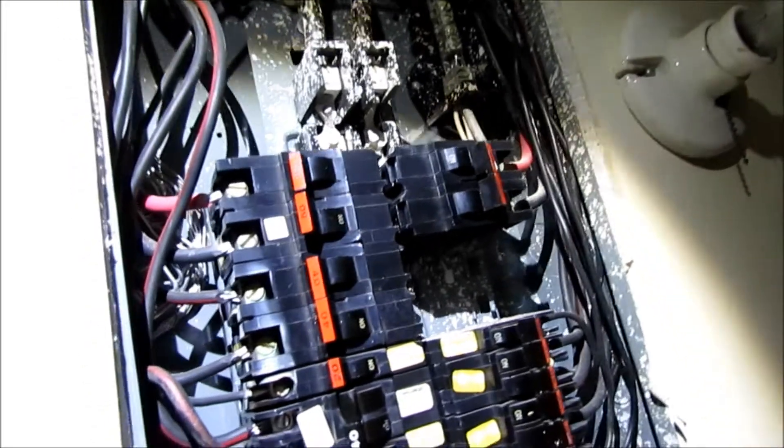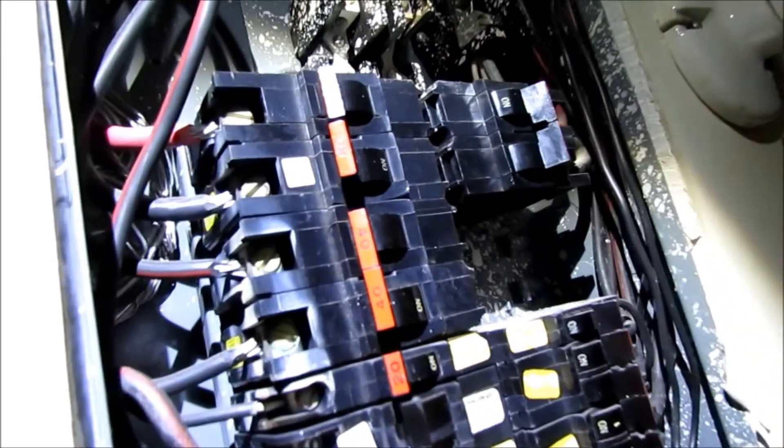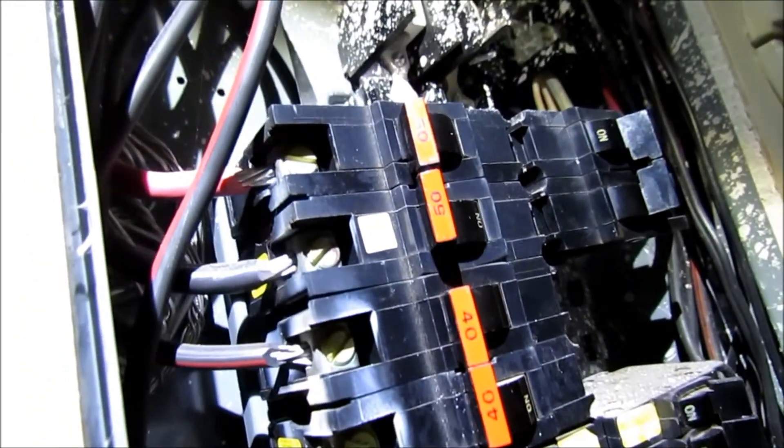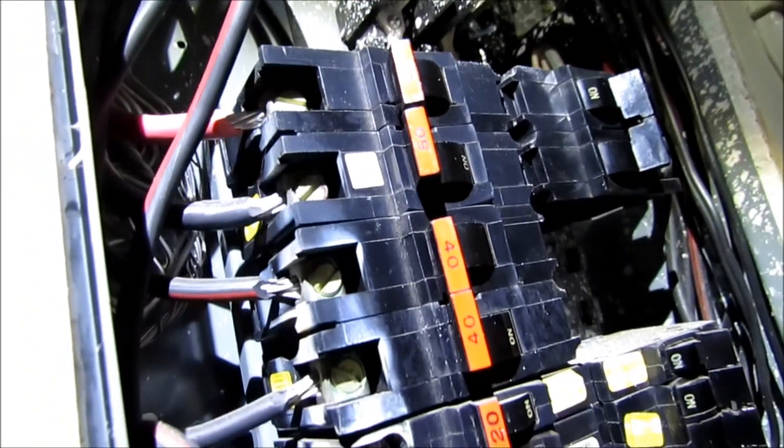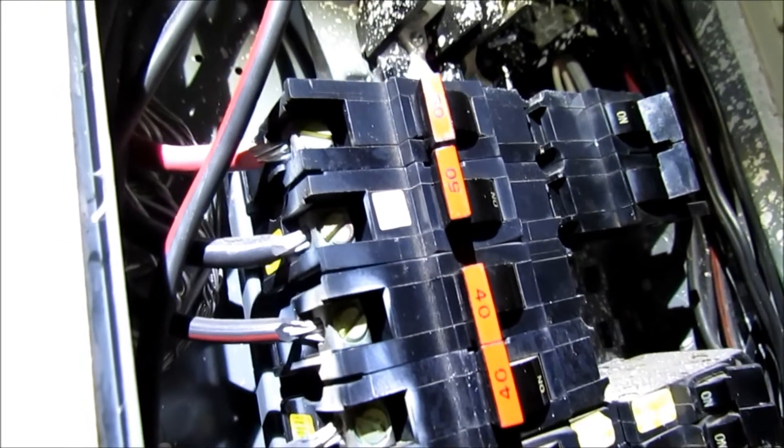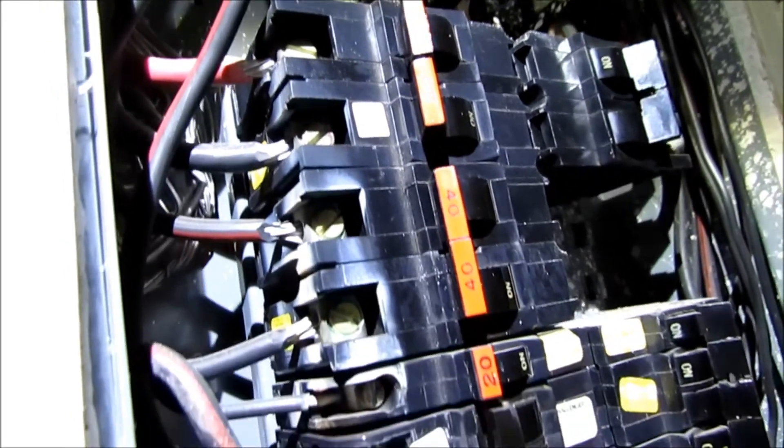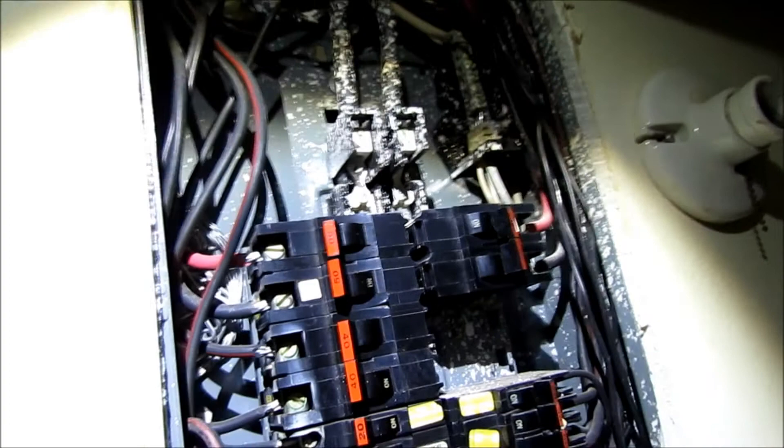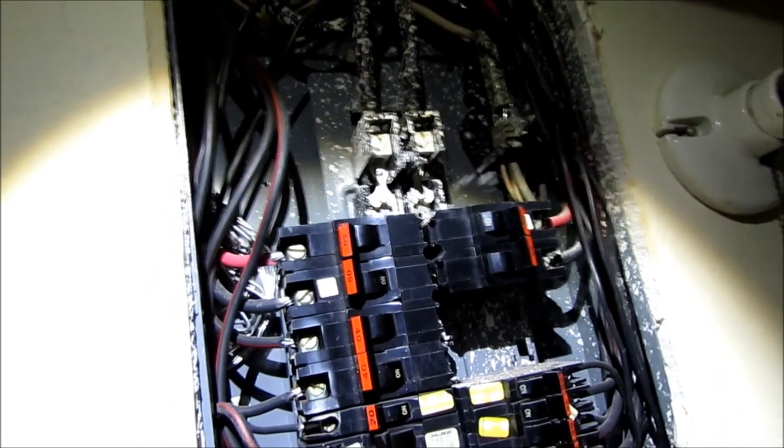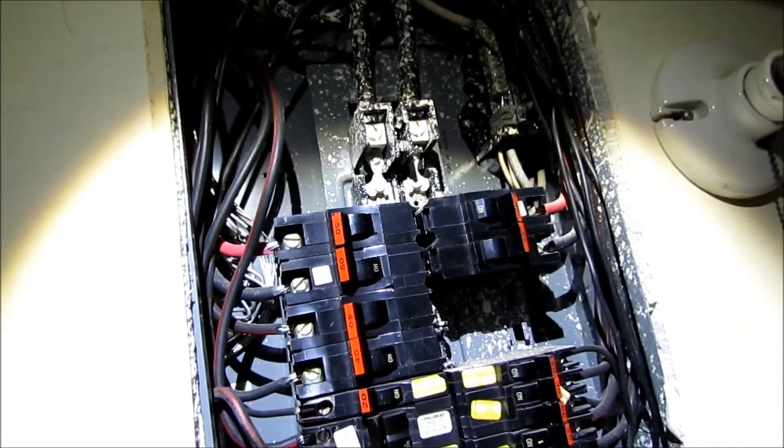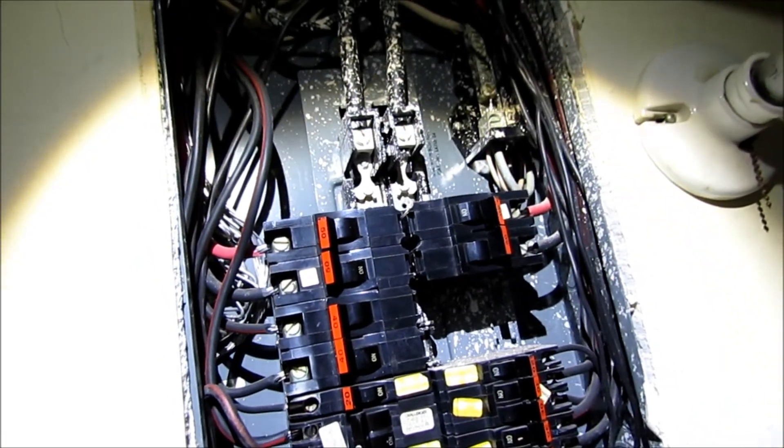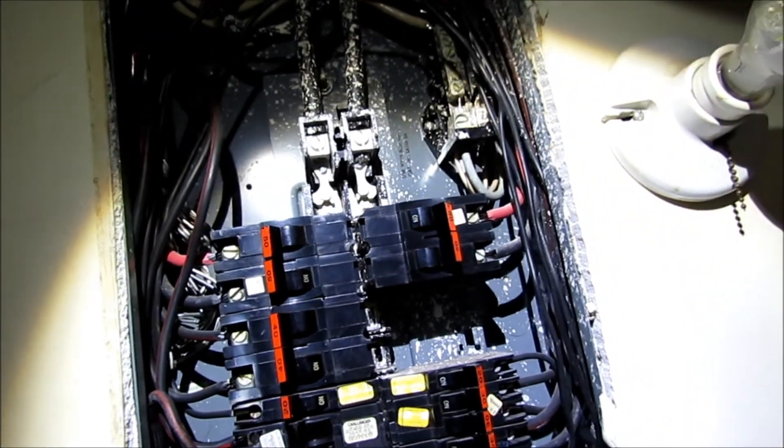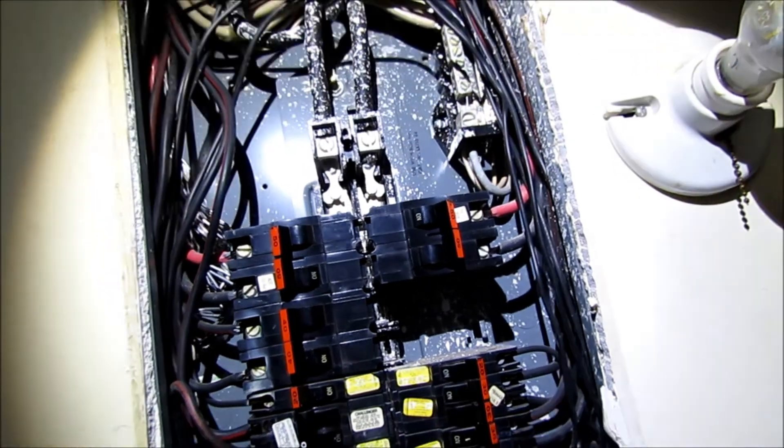And it also appears, looking right there, that those could be some heat marks where this breaker may have gotten overheated. And so that might be some of the things they've reported in the past as being a problem - sometimes the breakers are overheating as well.